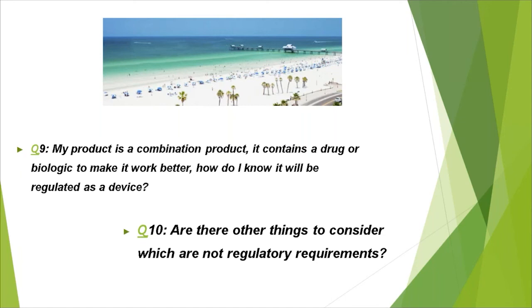And so for combination products where it's a little confusing whether it's a device or a drug, we like to try to get the device people involved early because often they want to think it's a device. Because sometimes you can look at a mode of action in two different ways. IVDs are also 510Ks, with the CLIA waiver request often reviewed by a different branch. And there are also 510Ks which are used for biologics like blood bags. Those can be submitted as a 510K, but they're reviewed by the biologic people at FDA.